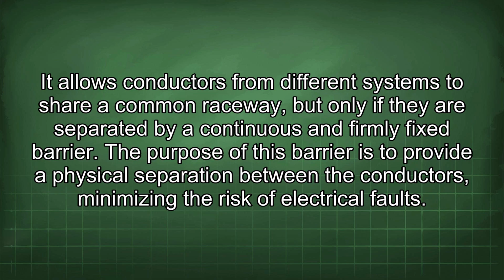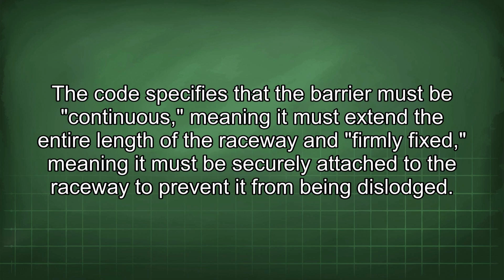The purpose of this barrier is to provide a physical separation between the conductors, minimizing the risk of electrical faults. The code specifies that the barrier must be continuous, meaning it must extend the entire length of the raceway, and firmly fixed, meaning it must be securely attached to the raceway to prevent it from being dislodged.